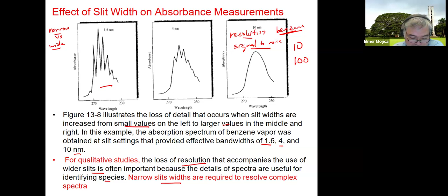The problem is if your resolution is high, your signal to noise ratio is low. If your resolution is low, the signal to noise ratio can be high. So you have to have some sort of compromise in this relationship between resolution and signal to noise ratio. In general, it is good practice to narrow slits no more than is necessary for resolution of the spectrum at hand. With a variable slit spectrophotometer, proper slit adjustment can be determined by acquiring the spectra at progressively narrower slits until maximum absorbance becomes constant.